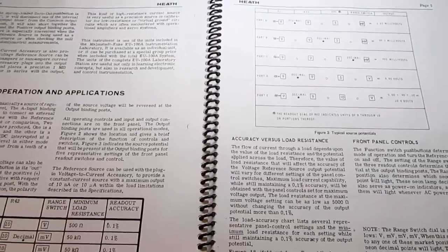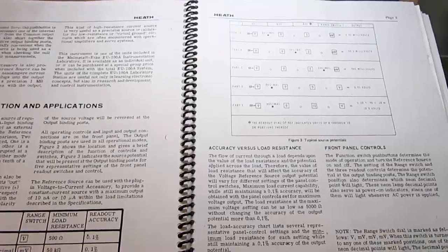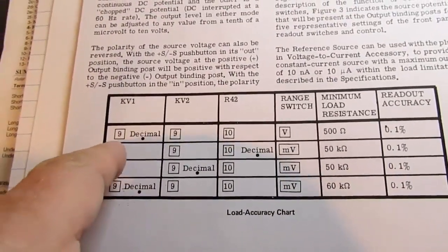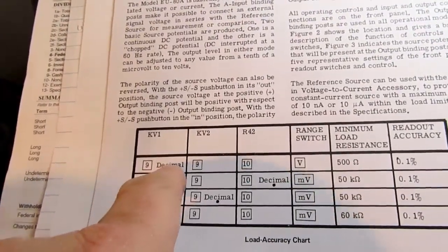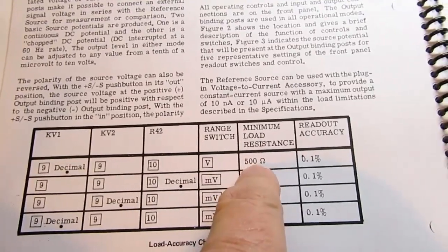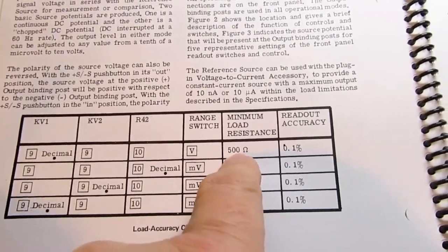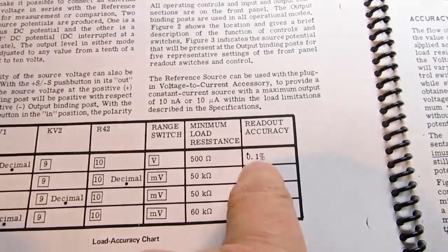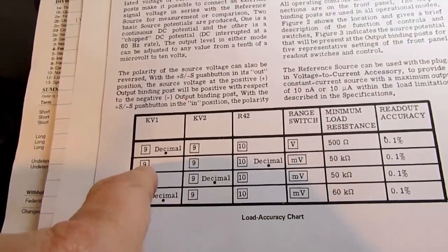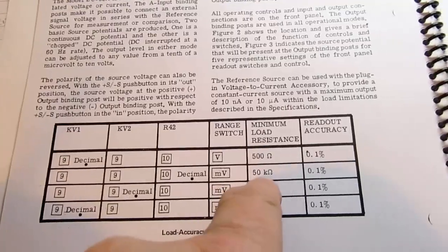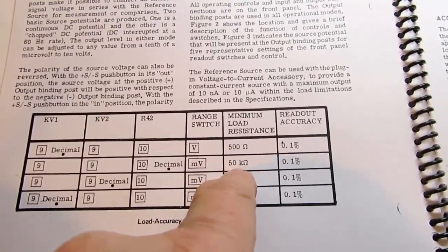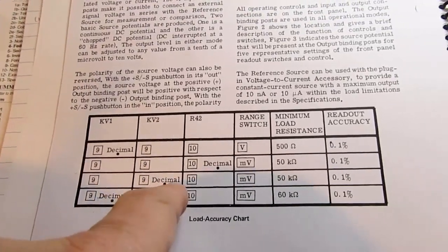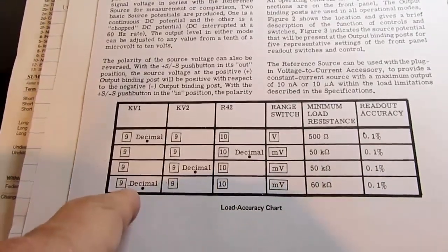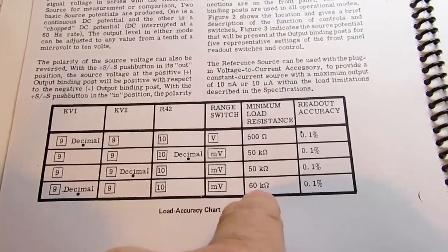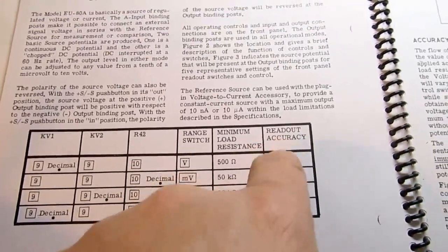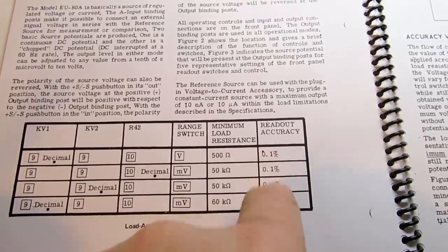Interestingly, the manual's specifications page does not mention the loading resistance, but this page does. So if you're in the 0 to 10 volt range, you need to have an output load no less than 500 ohms in order to keep the reading accuracy within 0.1%. If you're in the 1000 millivolt range or 1 volt range, the minimum load is 50k ohms. The same applies in the 100 millivolt range, also 50k. And in the 10 millivolt range, you should not have less than 60k ohms on the output. All of those will assure that the reading and the actual output are within 0.1% of each other.